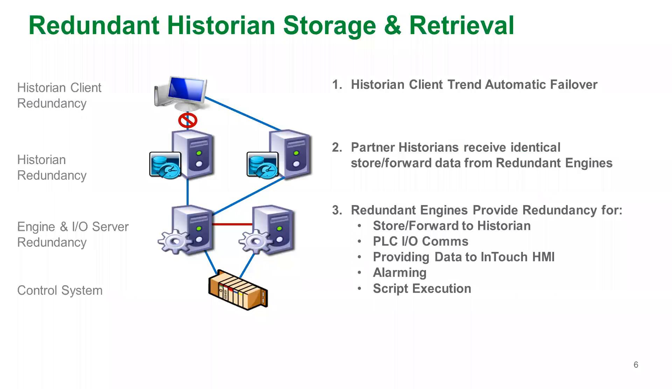Engines can also provide data to multiple historians so you have redundant storage and retrieval. If an operator loses a connection to their historian, their trends will automatically fail over to the partner historian. Let's take a look at this in action.